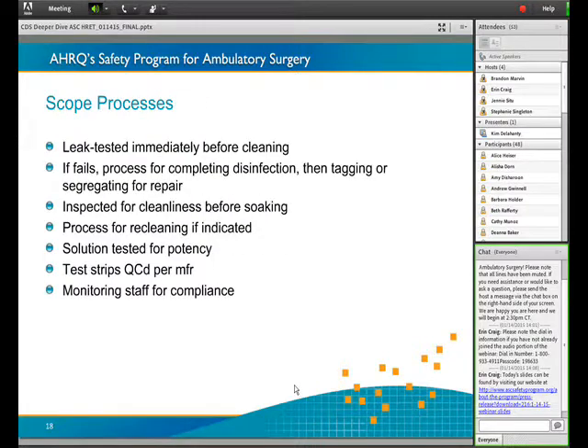The scope processes—if you've attended the other webinars, we've gone into detail, so we'll just do a quick review here. The leak test happens immediately before cleaning, and if there's any problem, meaning water is coming out through a sliver or hole in the scope, it's taken offline immediately and sent back to the manufacturer. If it fails the process for completing disinfection, you tag it and segregate it for repair. You want to make sure you do at least a pre-clean and enzymatic cleaning so that people at the manufacturer plant aren't exposed to blood, body fluid, or bioburden. That's the purpose of doing that first decon. Inspect for cleanliness before soaking.